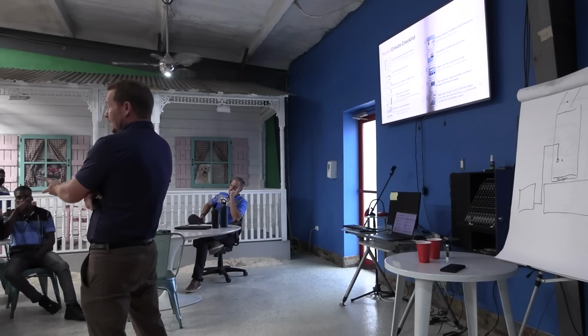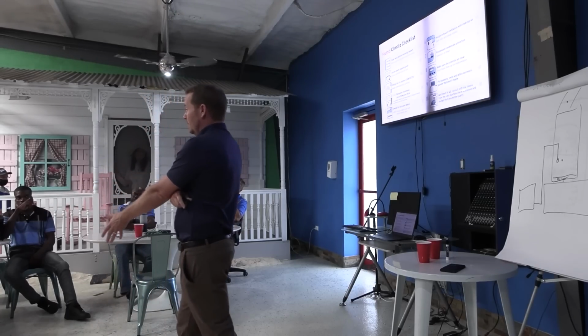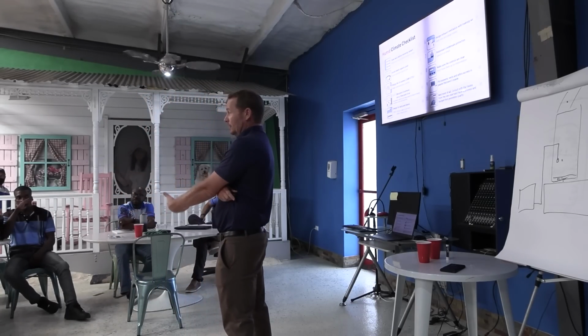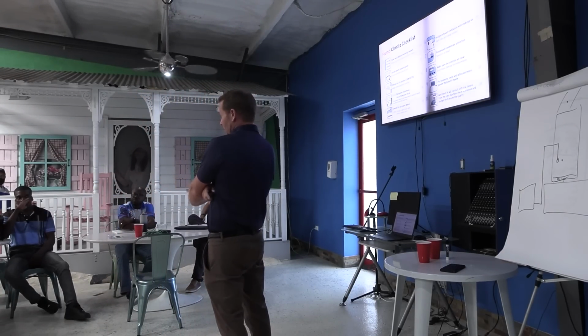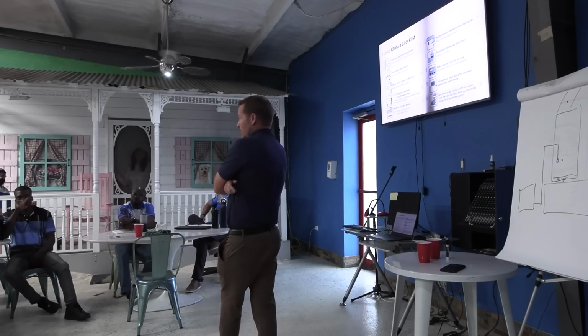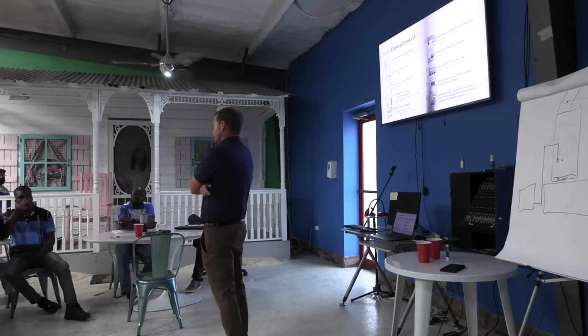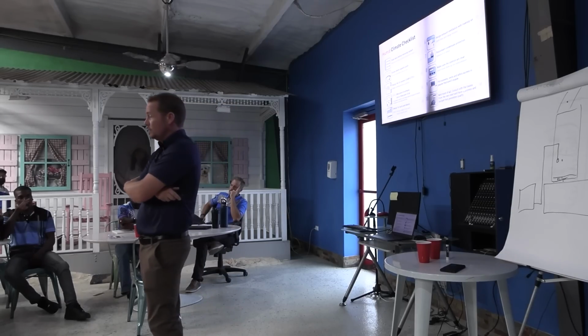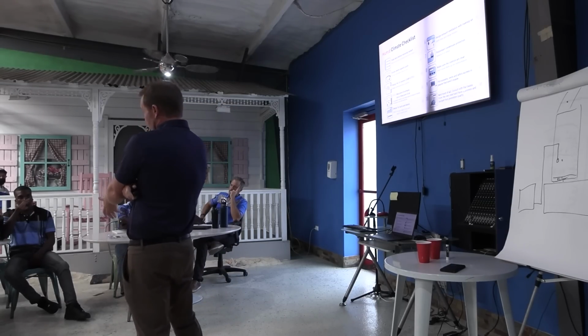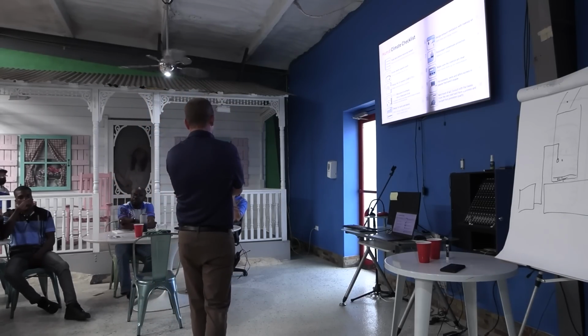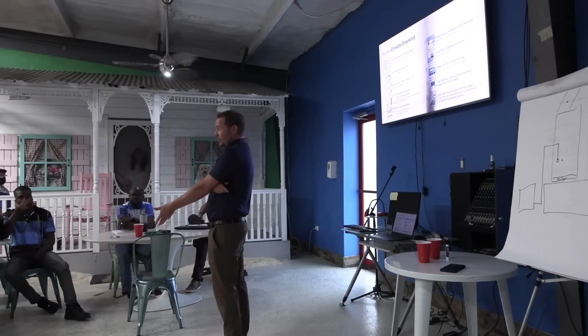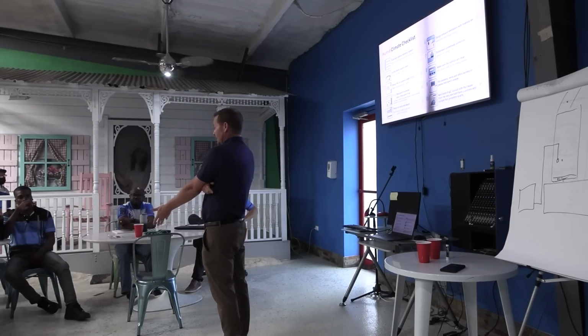It's not that they can't solve that problem. If they want to live that way, more power to them, but they're going to need a lot of supplementary dehumidification and probably upsized air conditioning. You can upsize air conditioning as long as you upsize the ductwork, and you can have a little extra load so long as you have a dehumidifier to fill those gaps. But you're going to spend a heck of a lot of money on equipment and on your power bills if that's how you want to live—that's your choice.